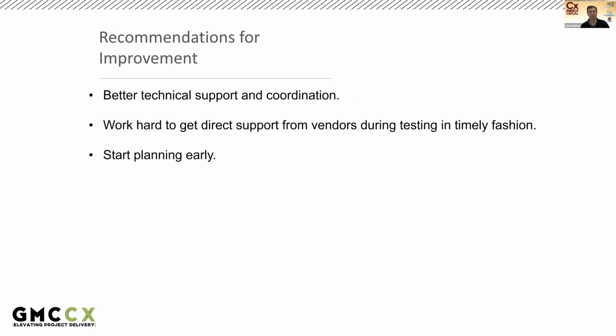Some of our recommendations for improvement: better technical support and coordination, with heavy controls integration meetings required from the start. For some contractors, it was their first microgrid. Some had battery storage experience, but not a lot with generators. So making sure that everything is coordinated early on is a huge recommendation. Work hard to get direct support from vendors during testing in a timely fashion. Like I mentioned, there are vendors not only from Tesla, but the controllers and the generator, so make sure that you get that support when you need it when you're doing the functional testing.